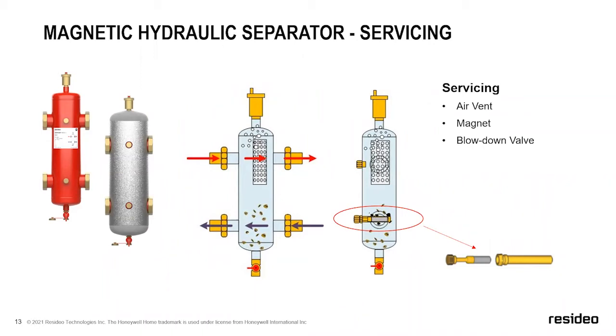It's a very different dynamic with a hydraulic separator. When the water enters, again, let's just use that 4 feet per second example, it's going to drop in velocity almost tenfold as it passes through the hydrosep. So if you're coming in at 4 feet per second, you may see 0.5 or 0.6 feet per second inside that vessel. So that's how the magic of these things works, that dramatic drop in velocity.